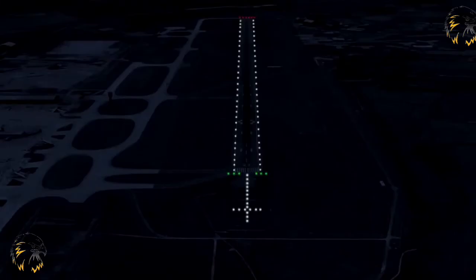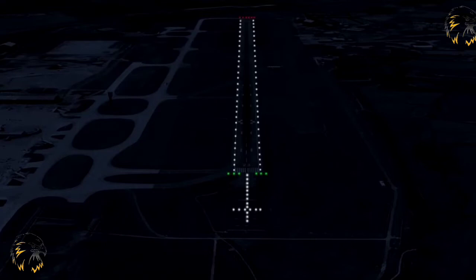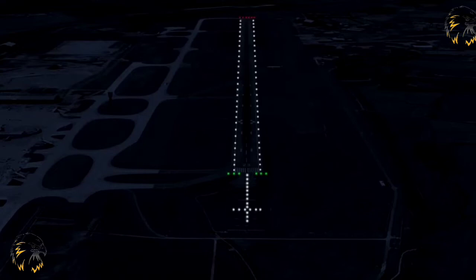A simple approach light system consists of a row of lights on the extended centreline of the runway extending for a distance of not less than 420 metres from the threshold, with a row of lights forming a crossbar 18 metres or 30 metres in length at a distance of 300 metres from the threshold. The lights of the crossbar will be bisected at right angles by the centreline lights. The centreline lights shall be placed at intervals of 60 metres, but if improved guidance is required, they may be placed 30 metres apart.